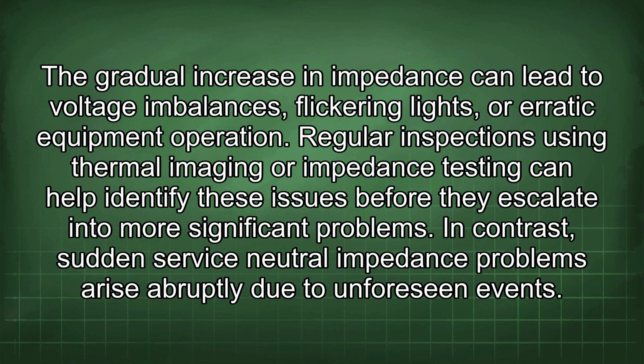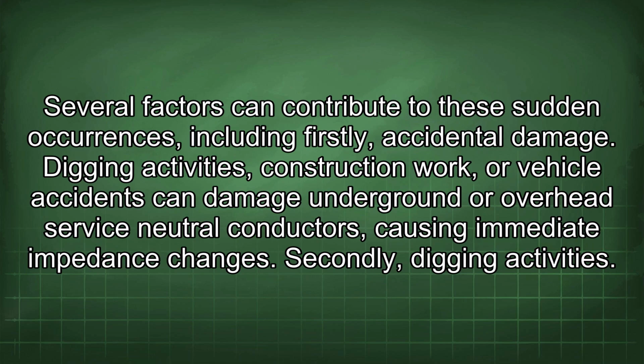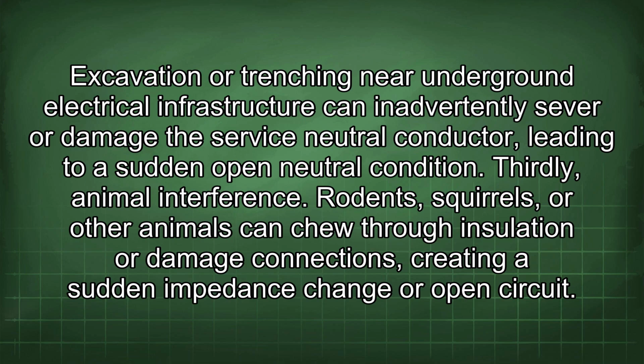In contrast, sudden service-neutral impedance problems arise abruptly due to unforeseen events. Several factors can contribute to these sudden occurrences, including, firstly, accidental damage. Digging activities, construction work, or vehicle accidents can damage underground or overhead service-neutral conductors, causing immediate impedance changes. Secondly, digging activities. Excavation or trenching near underground electrical infrastructure can inadvertently sever or damage the service-neutral conductor, leading to a sudden open neutral condition.